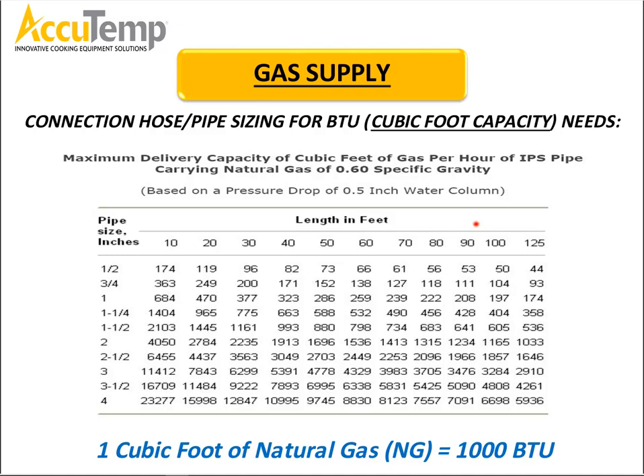It's gas supply, but it's also gas verification. I've got a great example that happened just this week. We had a customer purchase a brand new AccuSteam Griddle. They installed it, and the griddle wouldn't light. I got a call, so we sent service out there. Come to find out, they connected the griddle to a 2-pound system, meaning it had 56 inches of water column going to a griddle that can only handle 14 inches. It's the customer's responsibility at this point to replace the valve and add a regulator. But it's important to know what your pressure is and what that pressure can support.